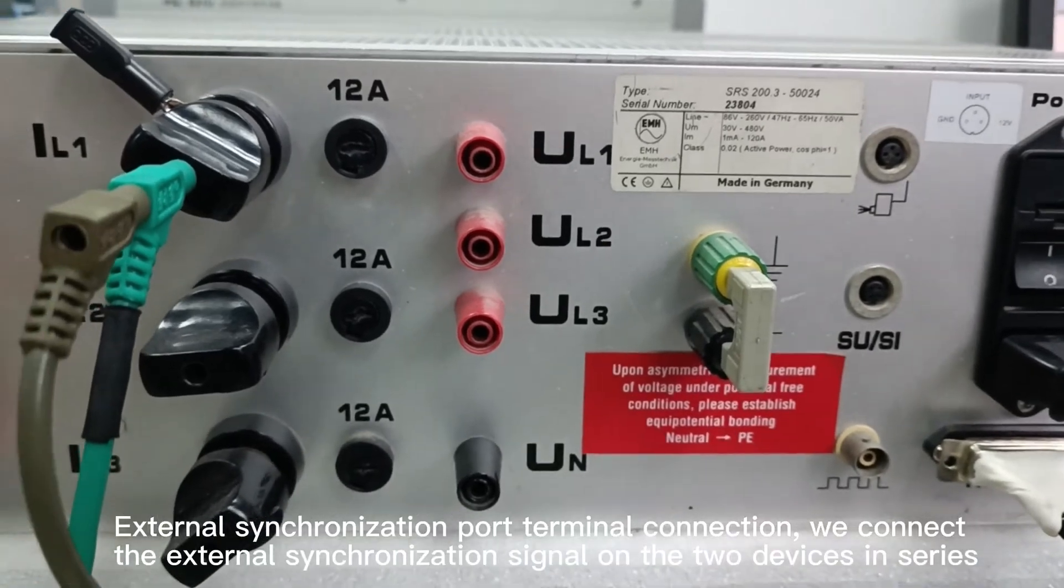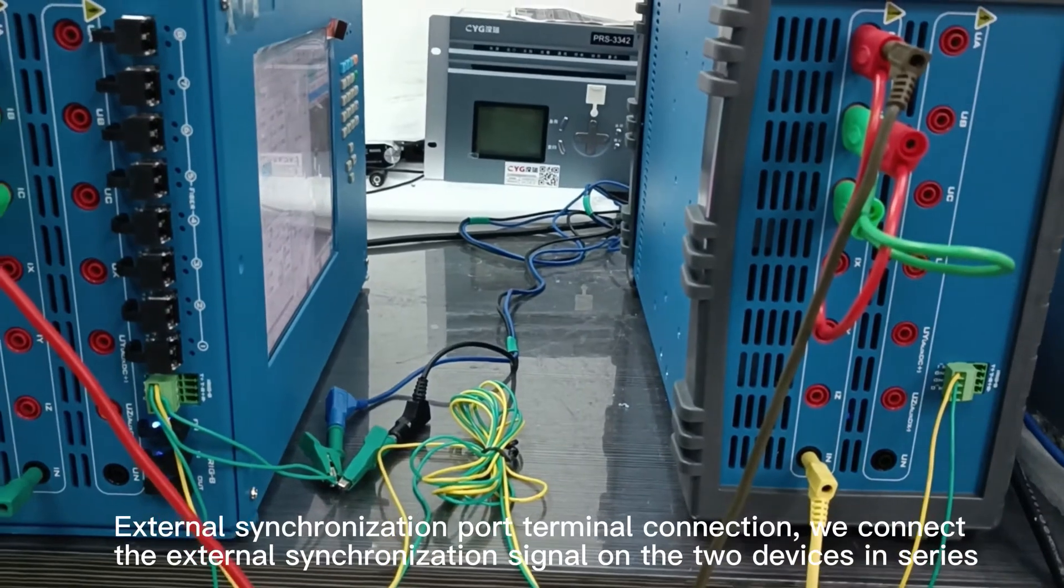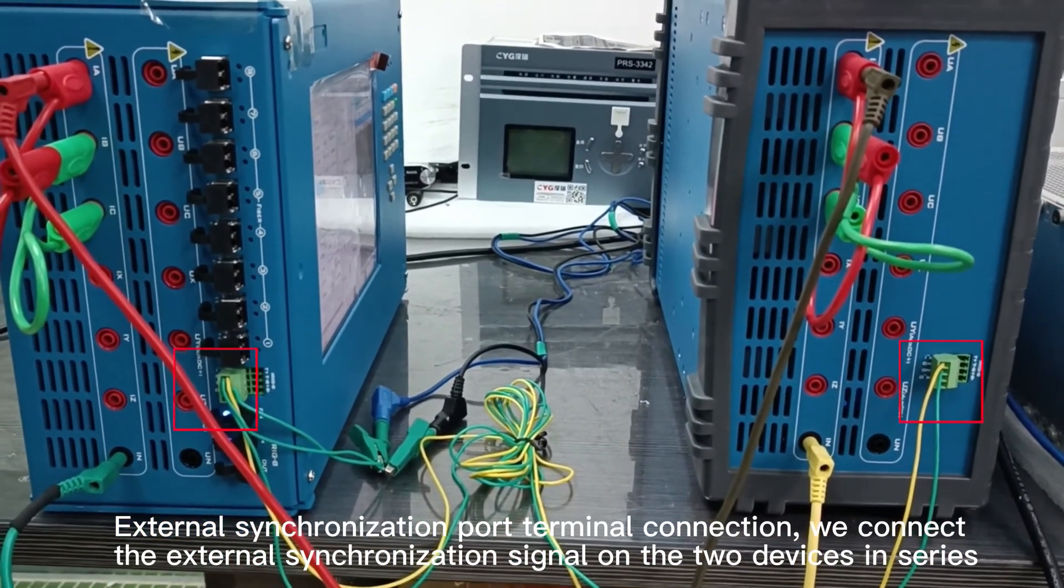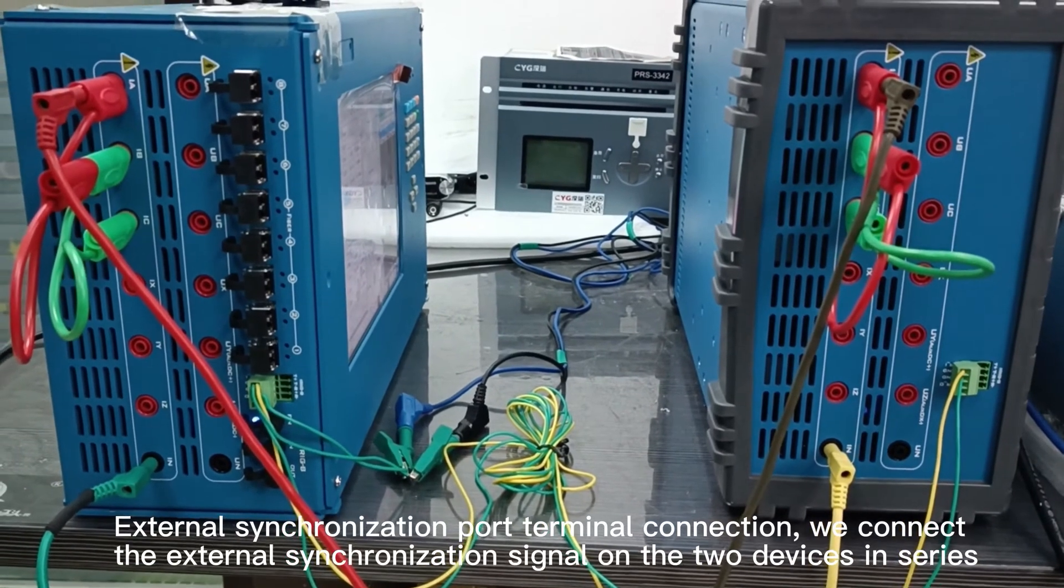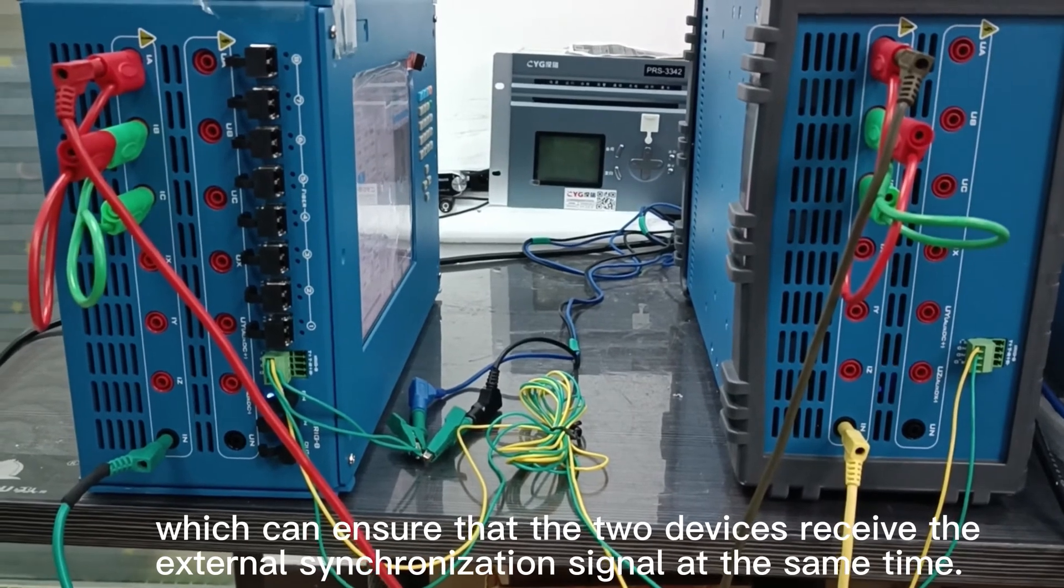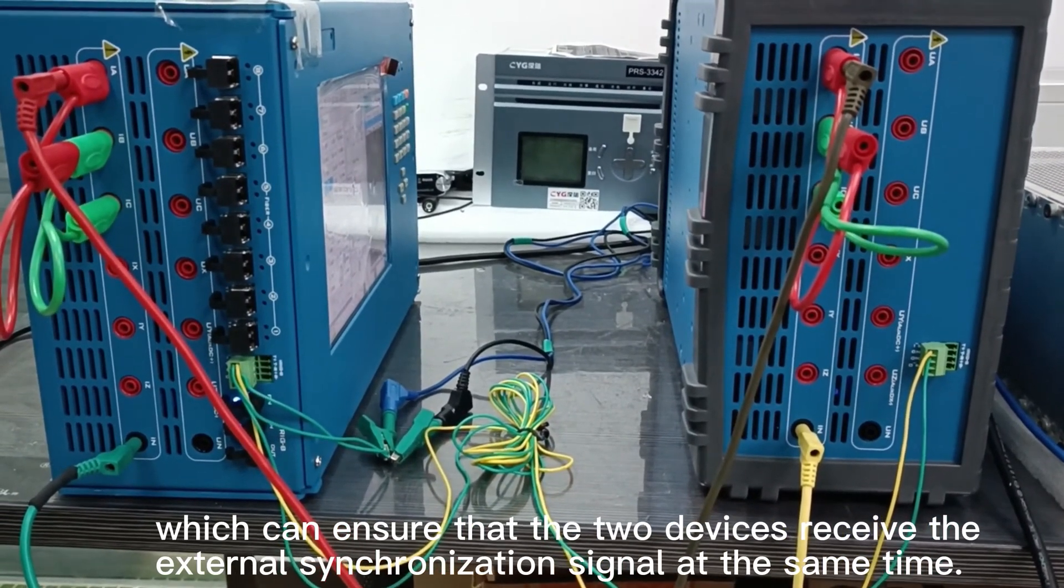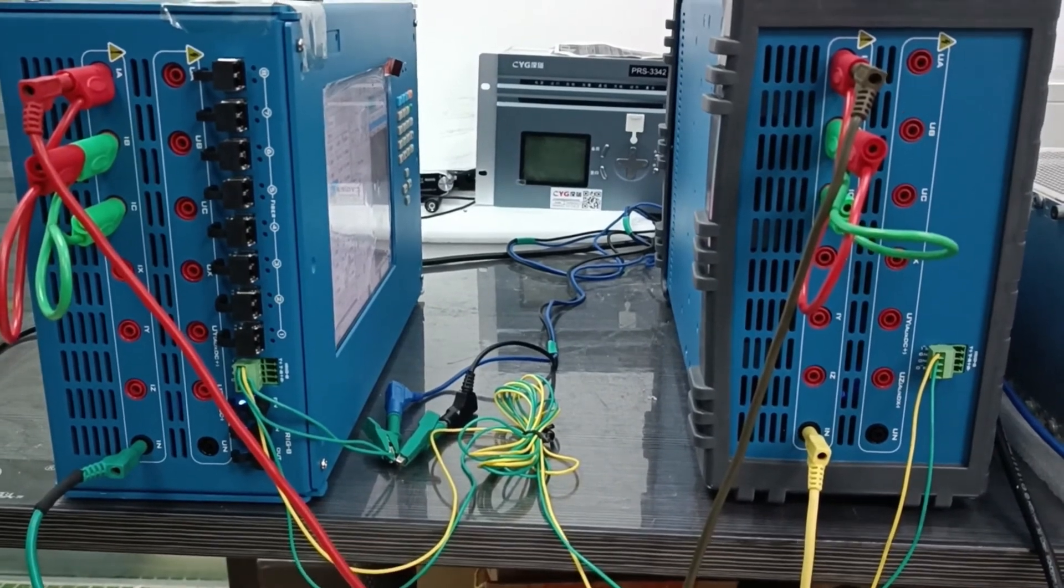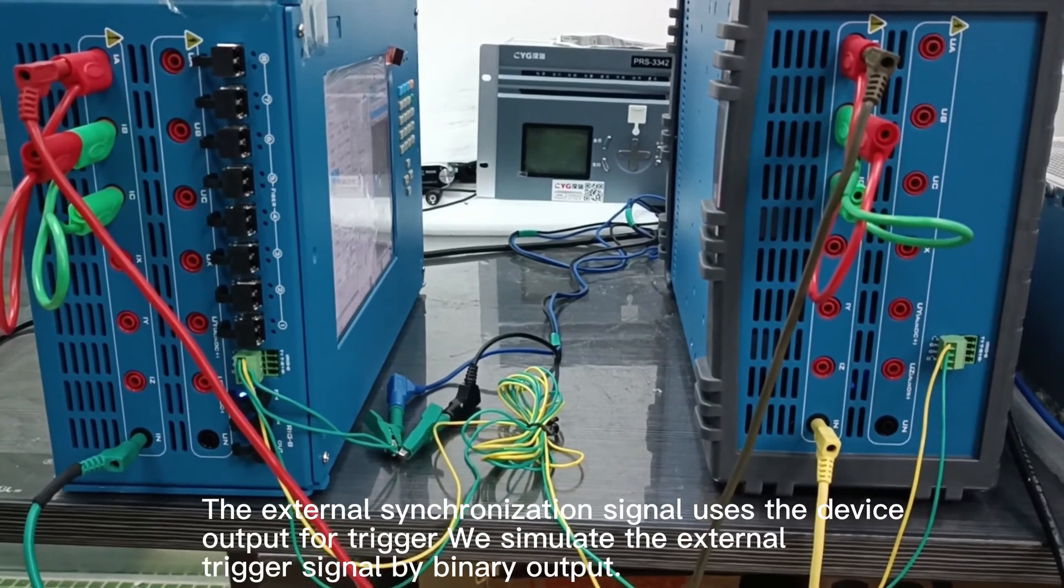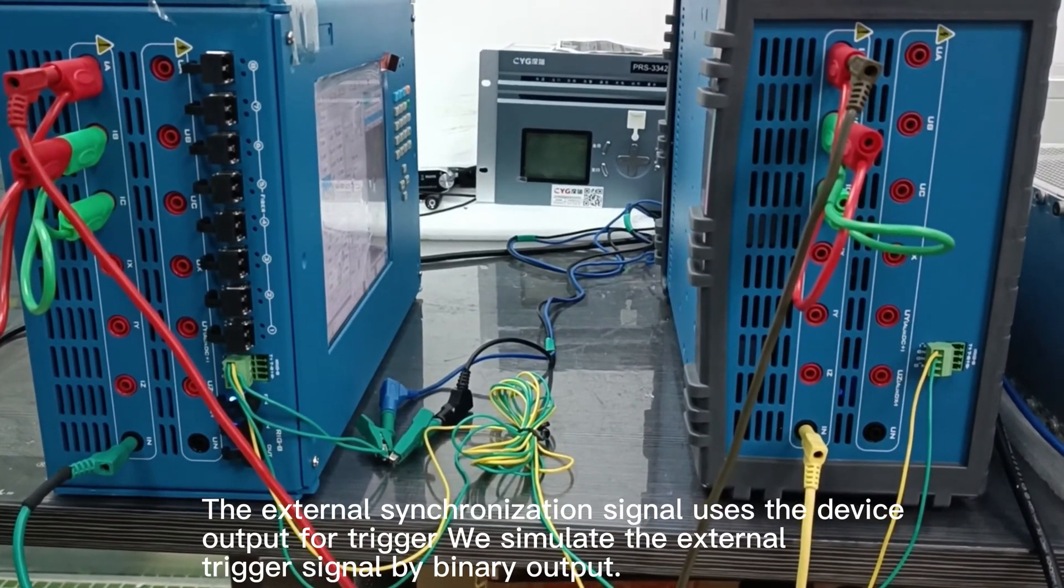Part two: external synchronization port terminal connections. We connect external synchronization signals on the two relay tester devices in series, which ensures that both devices receive external synchronization signals at the same time. The external synchronization signals use the device output for trigger. We simulate the external trigger signal by binary output.